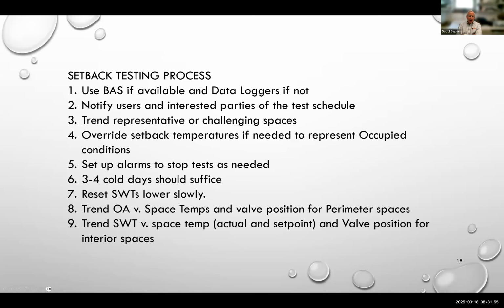So our setback testing process enumerated here is: use the BAS and data loggers if you have to. Notify the users and interested parties that you're going to do a test in case the temperatures get out of range and the alarm doesn't go, so they know it's a problem. Trend representative or challenging spaces like corner offices. Override setback temperatures if needed to represent occupied conditions. Set up alarms to stop a test as needed if it's in a critical space. And 3 or 4 cold days should suffice.